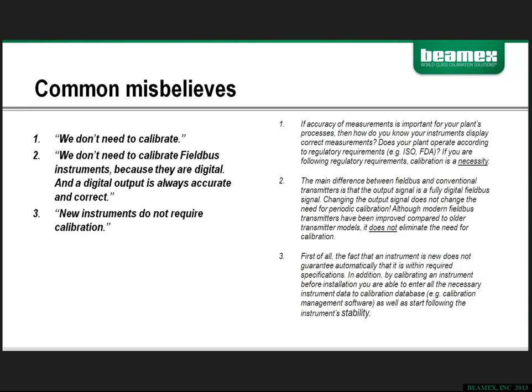Number three, new instruments do not require calibration. A new instrument may sit on a shelf, just as an example, for maybe a year before it's sold. It may be handled poorly by a carrier such as UPS or FedEx, or however it's delivered. It could have been exposed to any number of environments that could affect its accuracy. Initial inspection through calibration provides proof that the instrument is good before it is allowed into your process.